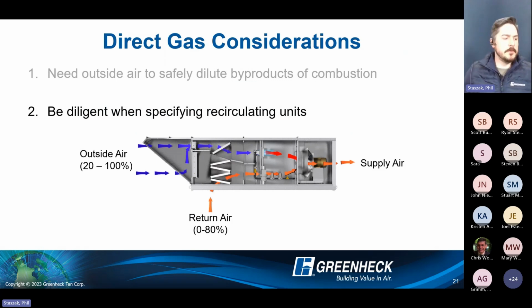Now, recirc: there's a lot of confusion around recirculation with direct gas fired. It can be utilized. It's called an 80-20 unit. I'm hoping you can see my cursor here, but the 20% portion is dedicated to this upper damper. Look at it as an inlet damper. Every time the unit is energized, that damper opens and brings in a minimum of 20% outside air, and then the remaining 80% is what we call a mixing box. It can either be the remainder of the outdoor air to do 100% outside air, or if this damper is fully closed, this one would be fully open. We can do a maximum of 80% return air, minimum 20% outside air, and anywhere in between.